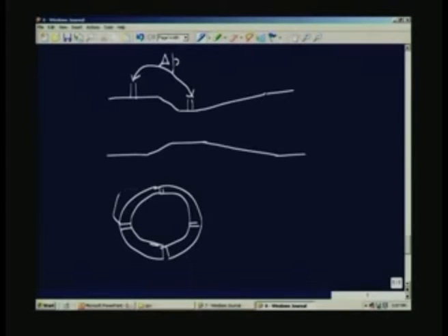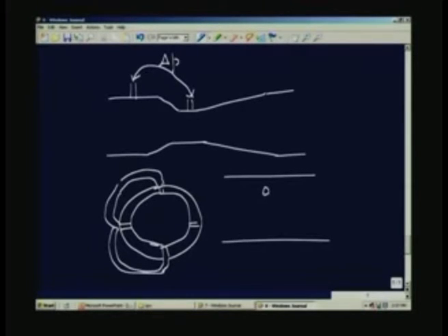That means that the pressures are all communicated to the same port, and that means that I am going to measure the average of the pressure in the 4 taps, in this case 4 or more than 4. So, if you look at the cross section of the pipe, the pressure taps will be there like that, and on the wall here, on the periphery, all of them are connected to the same port or the same hole, which is going to be connected to one arm of the pressure difference measuring device.